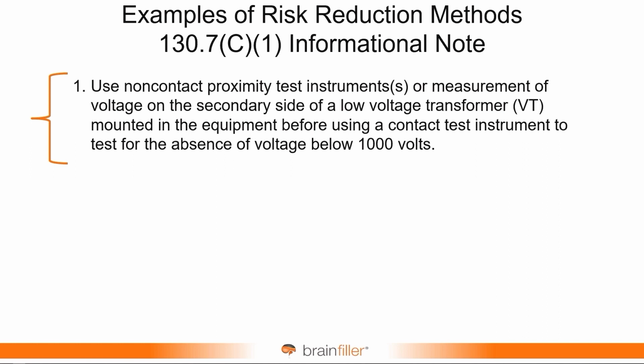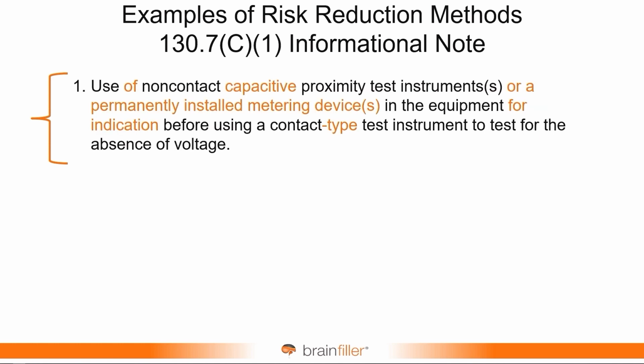It said non-contact proximity test instrument. It referenced low voltage transformers. Some may know this as PTs, potential transformers, and referenced up to 1,000 volts. Well, the 1,000 volts went away because this is not unique, whether it's above or below 1,000 volts. And the reference to the voltage transformer went away. But instead, it now states use of a non-contact capacitive proximity test instrument or permanently installed metering device, and the 1,000 volts went away.